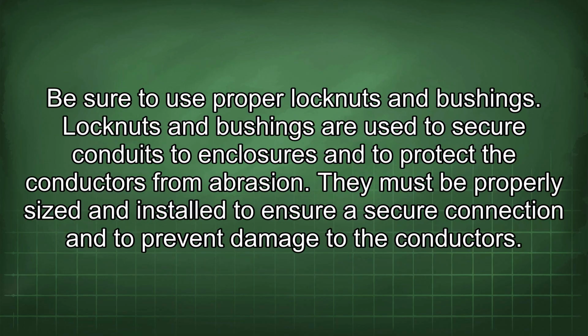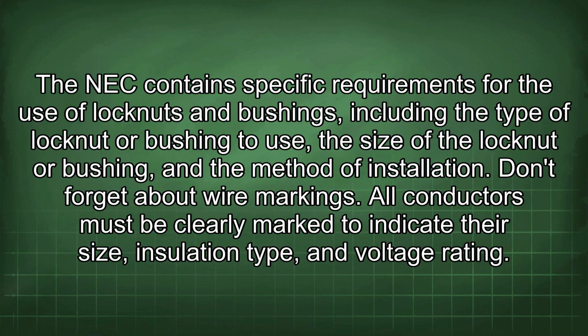Be sure to use proper lock nuts and bushings. Lock nuts and bushings are used to secure conduits to enclosures and to protect the conductors from abrasion. They must be properly sized and installed to ensure a secure connection and to prevent damage to the conductors. The NEC contains specific requirements for the use of lock nuts and bushings, including the type of lock nut or bushing to use, the size of the lock nut or bushing, and the method of installation.